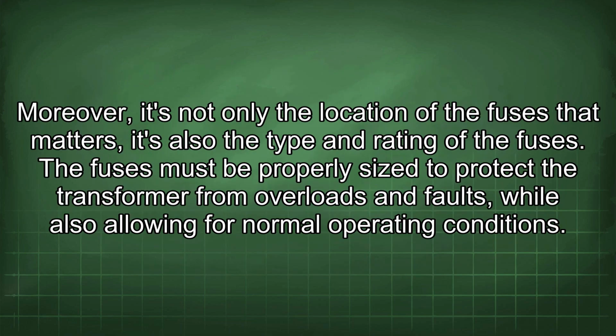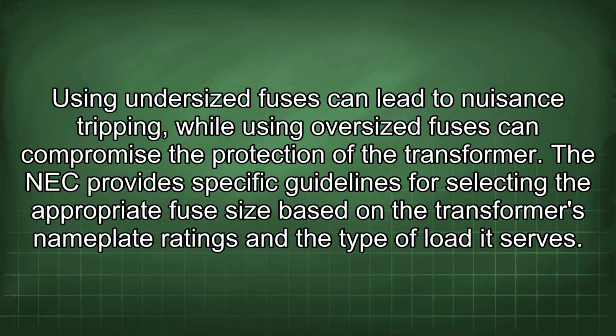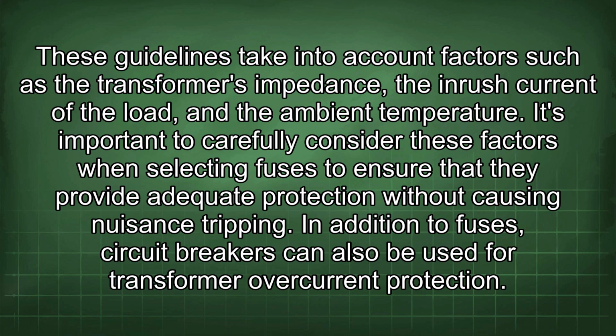Moreover, it's not only the location of the fuses that matters, it's also the type and rating of the fuses. The fuses must be properly sized to protect the transformer from overloads and faults, while also allowing for normal operating conditions. Using undersized fuses can lead to nuisance tripping, while using oversized fuses can compromise the protection of the transformer. The NEC provides specific guidelines for selecting the appropriate fuse size based on the transformer's nameplate ratings and the type of load it serves. These guidelines take into account factors such as the transformer's impedance, the inrush current of the load, and the ambient temperature. It's important to carefully consider these factors when selecting fuses to ensure that they provide adequate protection without causing nuisance tripping.